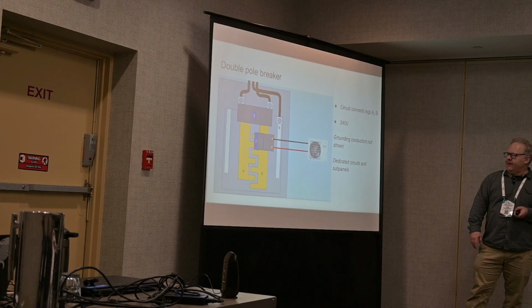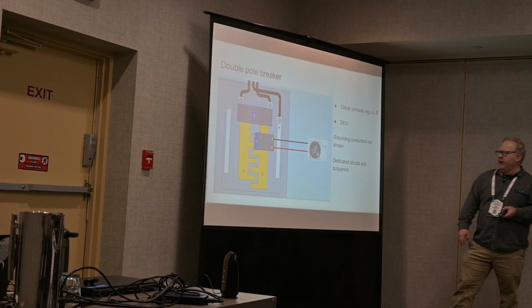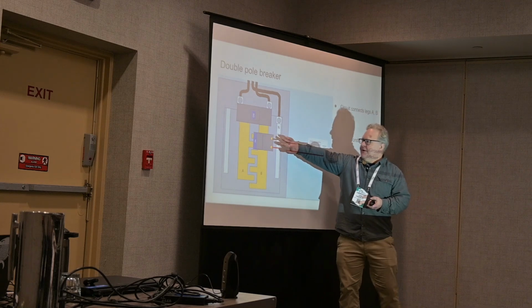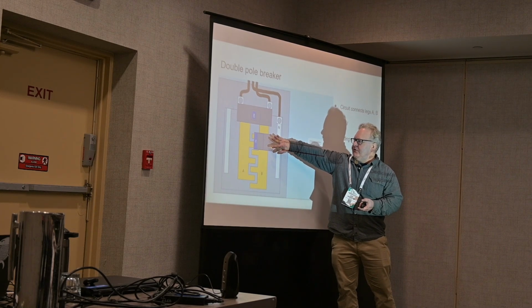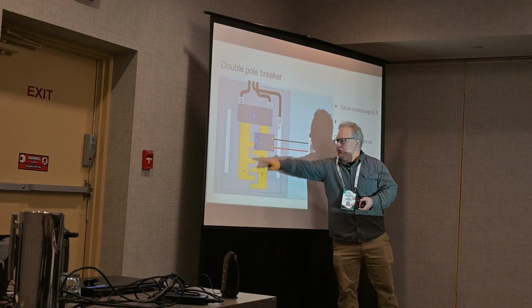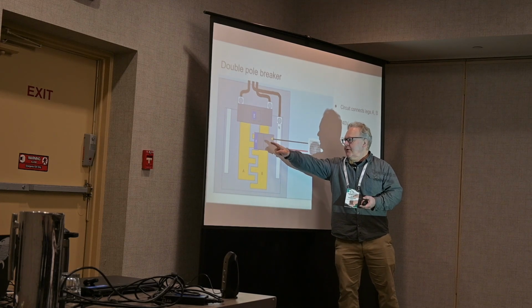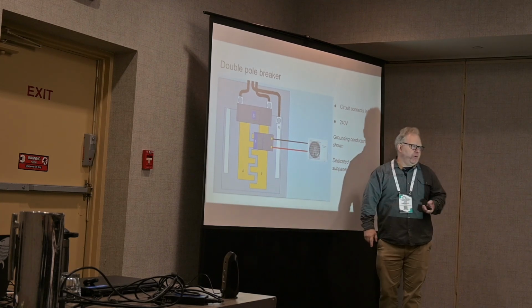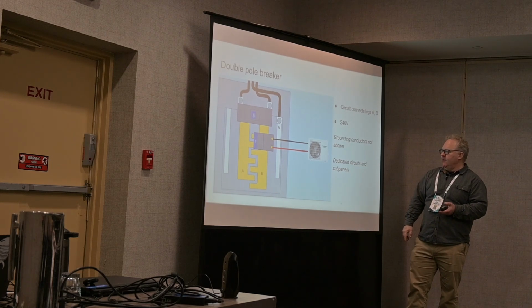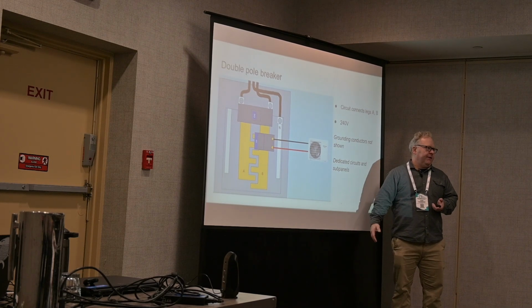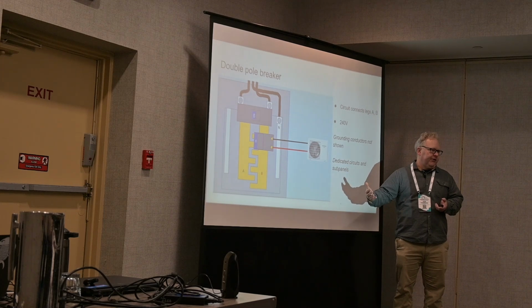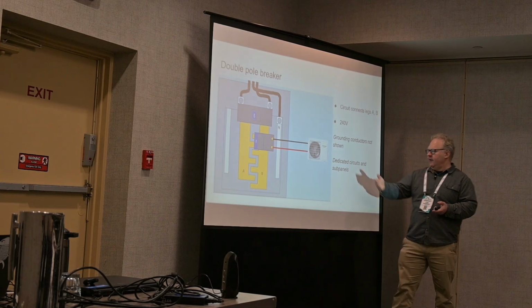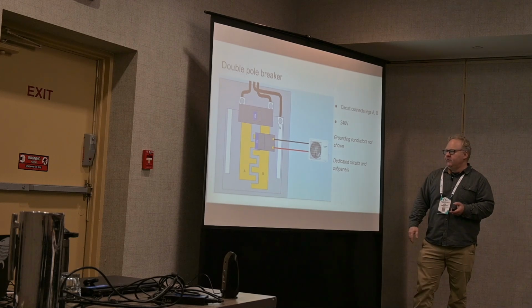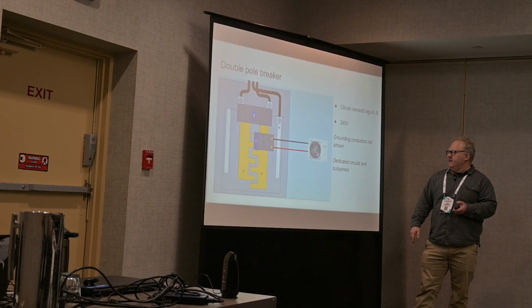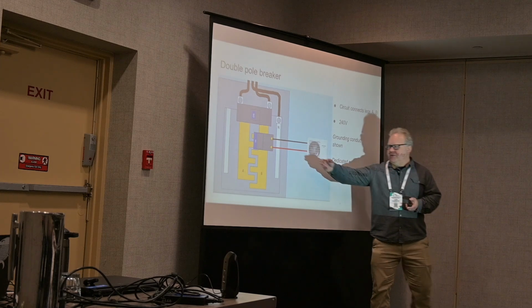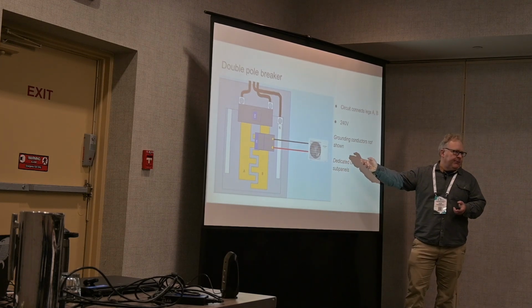When we have a double pole breaker, this is a breaker that covers two spaces. It connects one leg of power to the other, and between those we have 240 volts. And this is what we're going to have for things like heat pumps, heat pump water heaters, electric dryers, things that are heavier duty loads. We also are going to use these double pole breakers if we're going to install a sub panel.